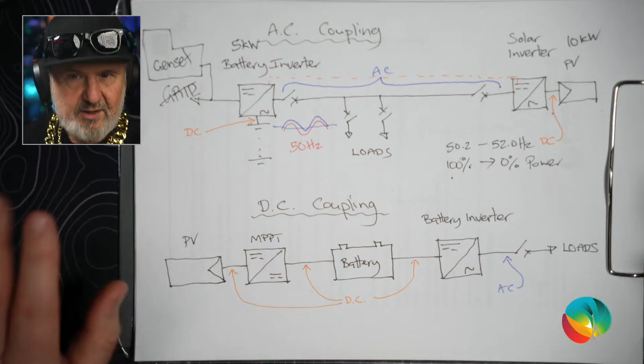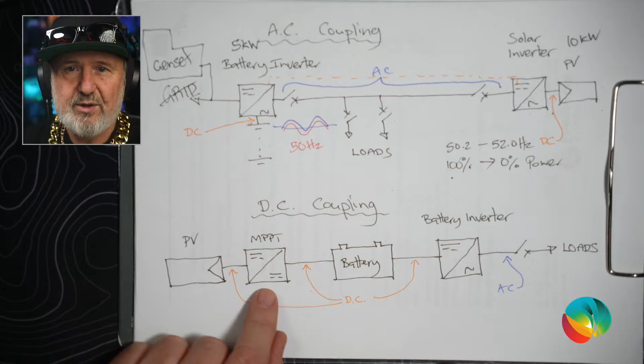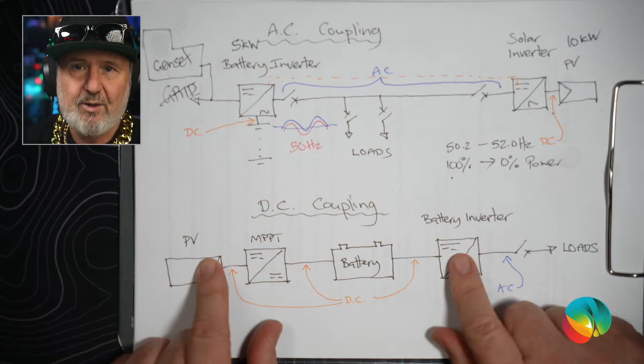DC coupling. Now, DC coupling was actually the only way you could charge a battery up until about 20 years ago. You would have a solar array. You would have what's generically referred to as a charge controller. I'm using an example here of a maximum power point tracking charge controller, which gives you some other advantages in terms of getting the most power out of your PV array and also being able to match voltages. So if the PV array is operating at 120 volts and the battery is operating at 12, it can match them. So either side of the MPPT can be different voltages.